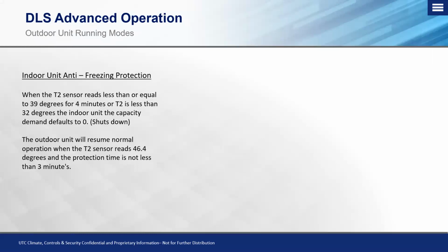Essentially what it's doing is it's looking at that T2 sensor and saying, hey, if my reading is less than or equal to 39 degrees for 4 minutes, the system realizes that it's tried to throw countermeasures at it and it can't do it. Or if that sensor reads less than 32 degrees, the system realizes that that, of course, is our freezing point. We don't want to freeze that indoor coil. The system shuts down as a preventative measure.